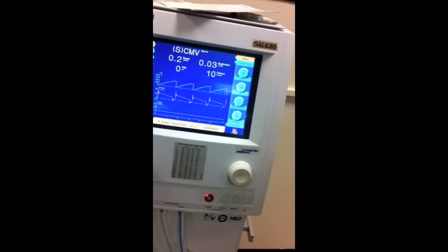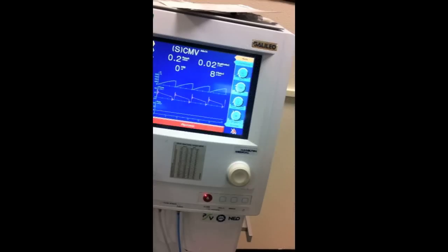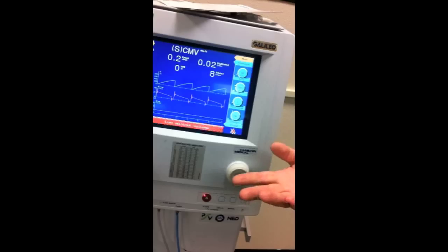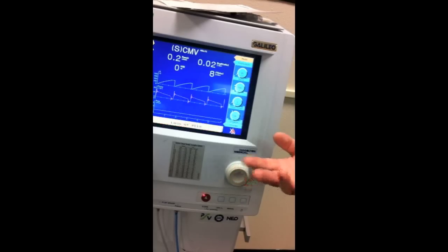One of you guys? The servo and the PB, everybody has their own little calibration that takes you right through. This one we do the old-fashioned way. I'm not going to do them all, but you guys will need to go through this. It's going to tell you to turn it on, come up to the screen where it says self-test, and then put standard setup so that the ventilator starts.